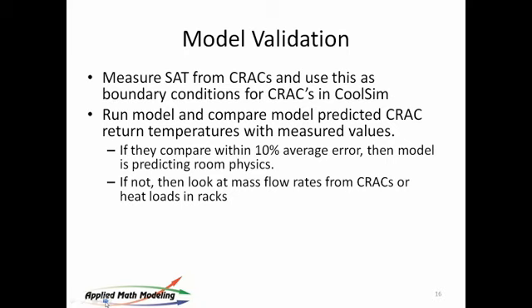Put a probe under the floor in a raised floor case and measure what the cold air temp is. You also want to measure the return temp at that same point, because we're doing an instantaneous point here. We're looking at it at one point in time. To be honest, the supply air temp varies depending on whether the compressor is on or off. But if you take a snapshot in time and then build a model based on the snapshot and validate your data, at least you know that the physics are being captured by the model.